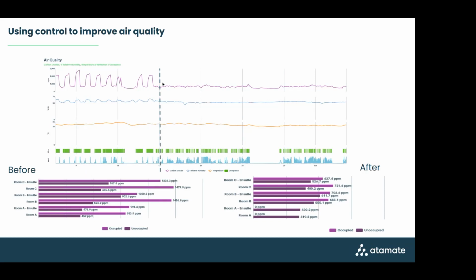And then we've got this before and after again - this is some flats accommodation. Roughly speaking, the top purple line is when it's occupied, and this is carbon dioxide levels - around 1300, 1400. So you get the idea, around 1,000 parts per million when occupied, and around 600-700 when unoccupied.